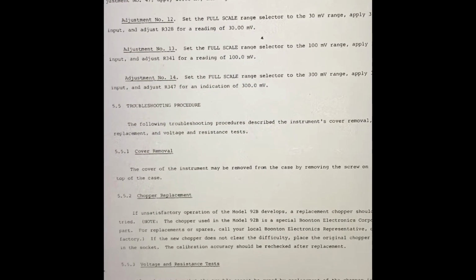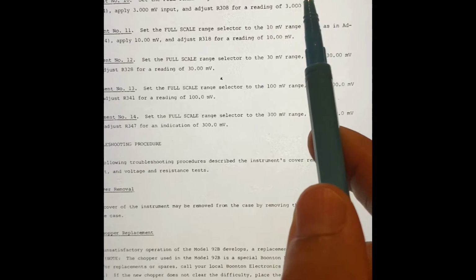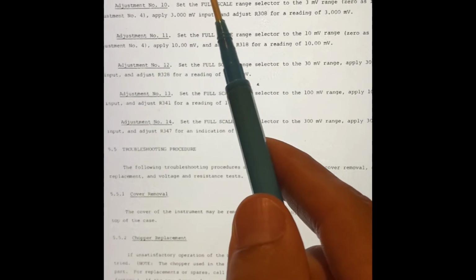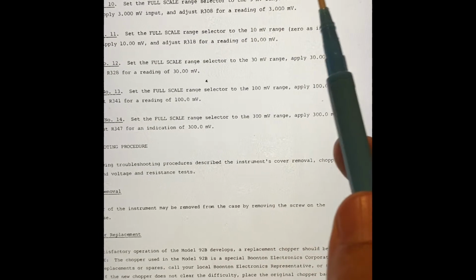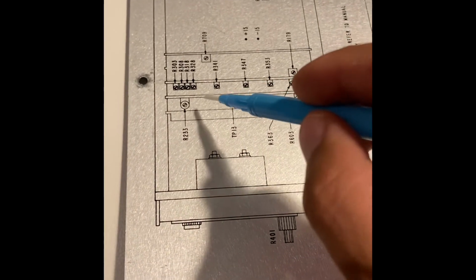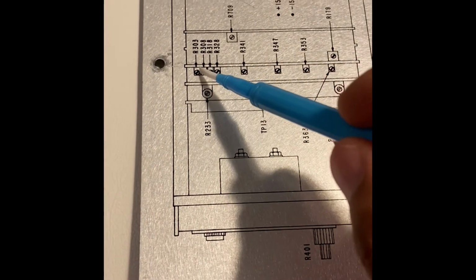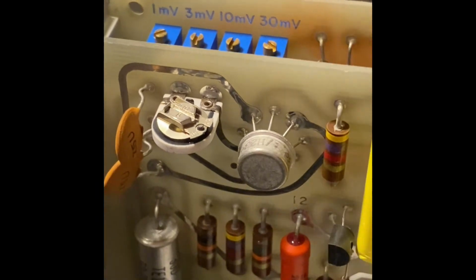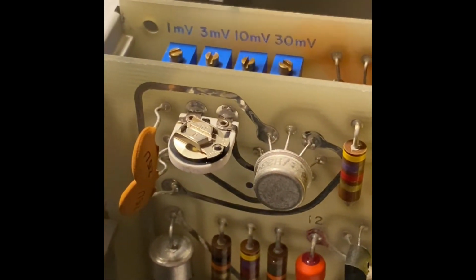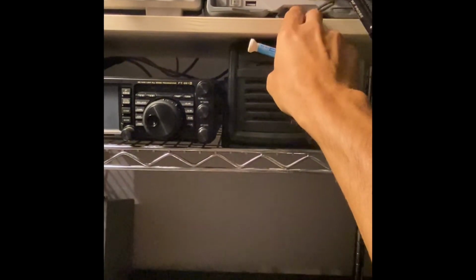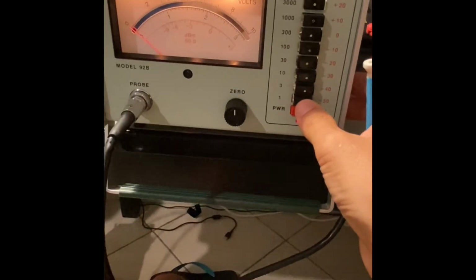Next, adjustment number 9. Set the full scale range selected to the 1 millivolt range, zero the instrument, and apply 1 millivolt. Adjust 303 for 1 millivolt reading. So now we go down to the bottom of the range, and 303 should be the first one. It is indeed 303, and you can see those are also well marked on the board. So 1 millivolt, we go, let me switch off the signal gen there, and we go to 1 millivolt, and let me set it all up.